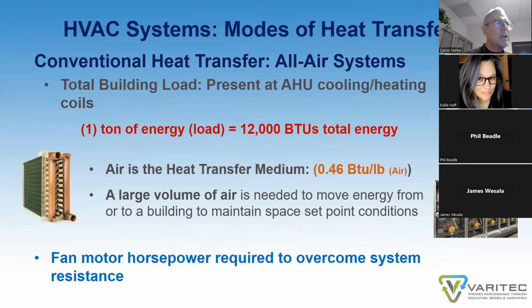In a conventional heat transfer mode, an all-air system, total building load is present at an air handler or a package DX unit coil. It's either a cooling or a heating coil. And we also talked about 1 ton of load, total energy, which is sensible plus latent energy, being equal to 12,000 BTUs of energy. So in a conventional system, if we want to move energy from a building to outdoors in cooling, air becomes the heat transfer medium. We cool the air to a low enough temperature and supply it to a building to remove the heat gain in that building.